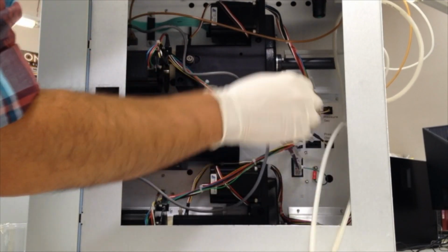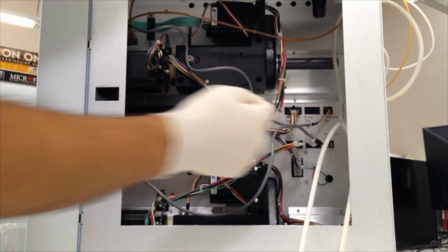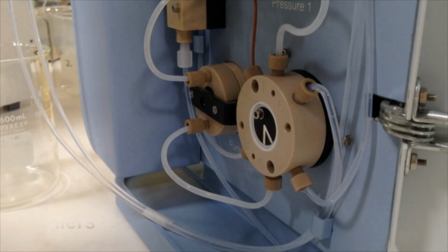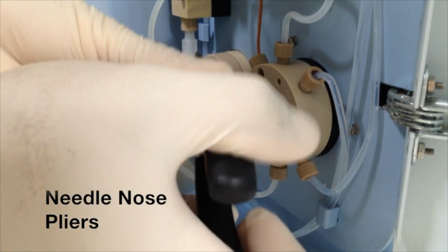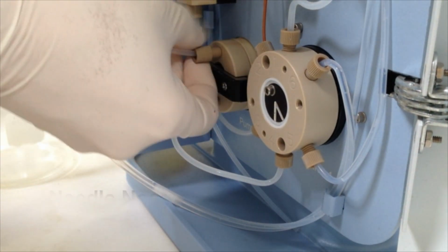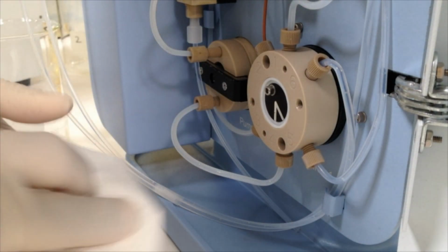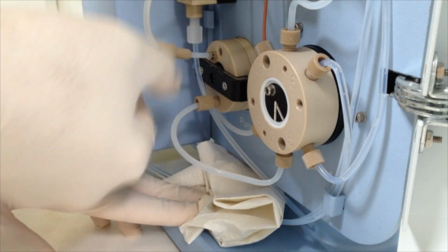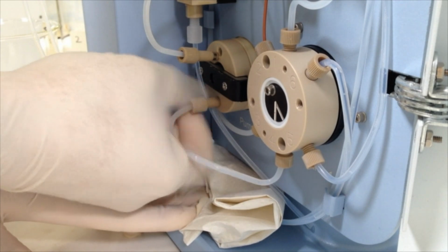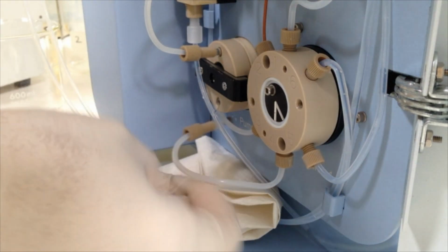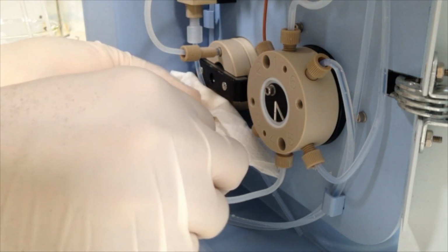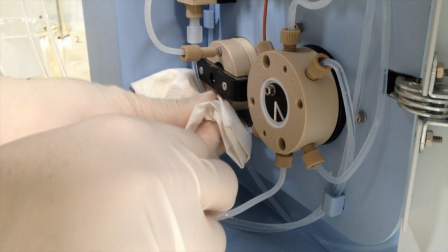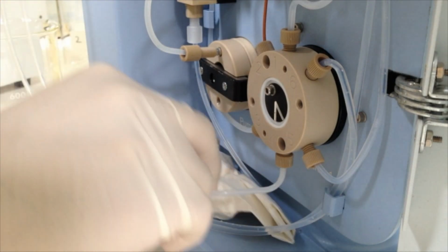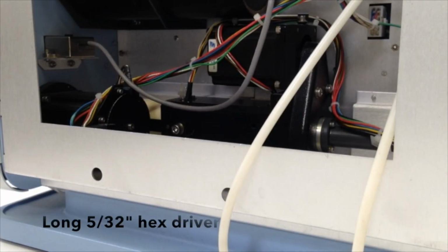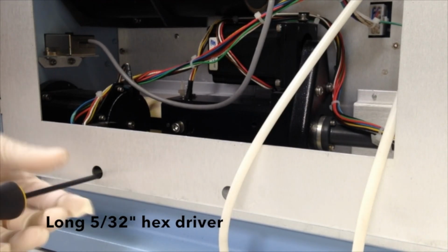Next, remove the pump connections to the control board. Completely remove all tubing connections to the pump and valve. You may need to use needle nose pliers to loosen the nuts. Place a paper towel underneath the pump and valve to absorb any excess flush solution. Use a long 5/32 inch hex driver to remove the 3 screws holding the pump to the chassis.